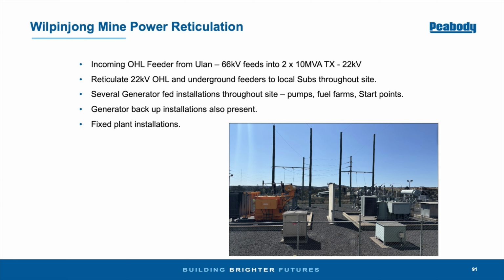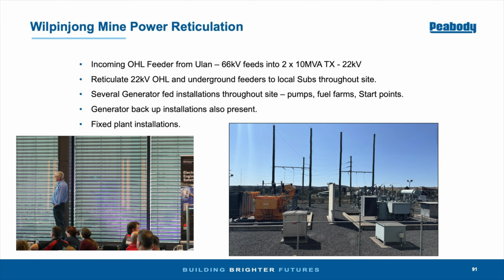So the mine's power reticulation: it's an incoming 66 kV, going into two 10 MVA transformers. The mine was expanded in 2011, so the original 66 to 22 is on the right-hand side. When expanded, they put in a sister transformer next door, feeding into two switch rooms, with a bus tie between them so we can run independently off either one. We only draw about 5.5 maximum, so it's pretty good from a maintenance point of view - I can isolate one complete side off and still have the other one there.